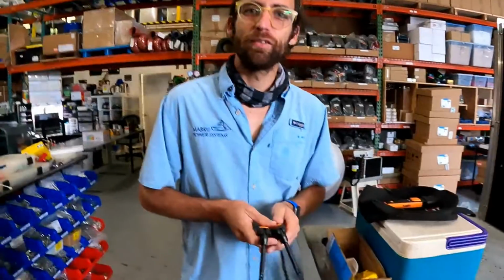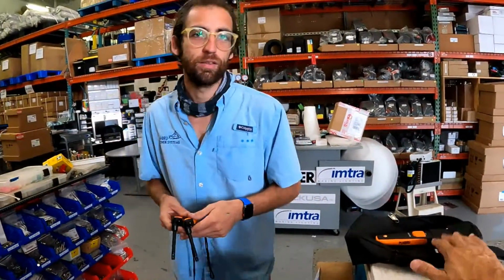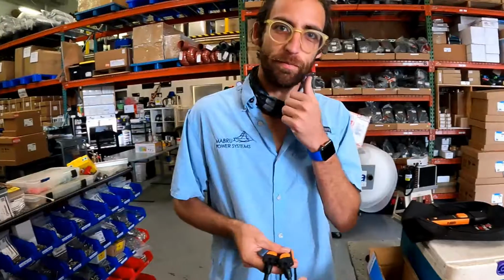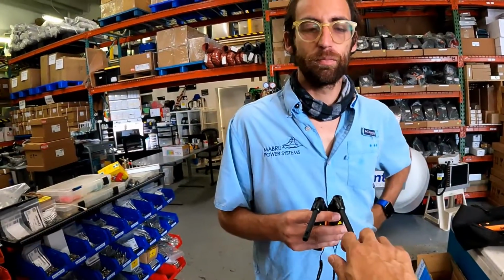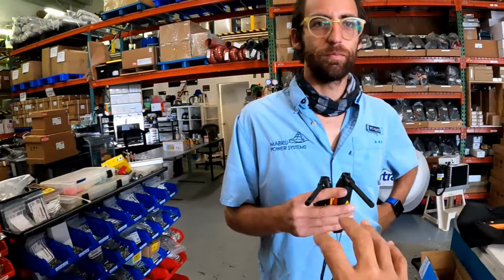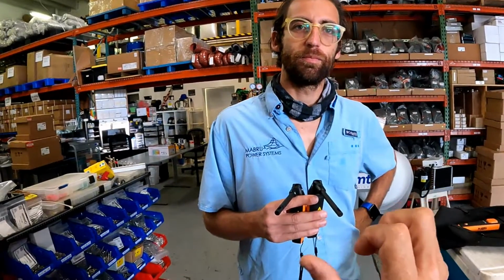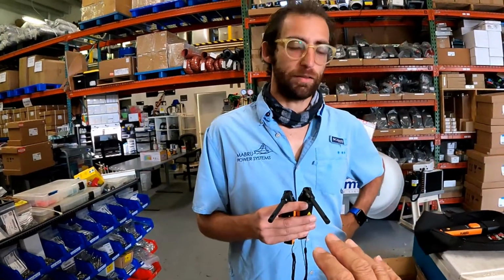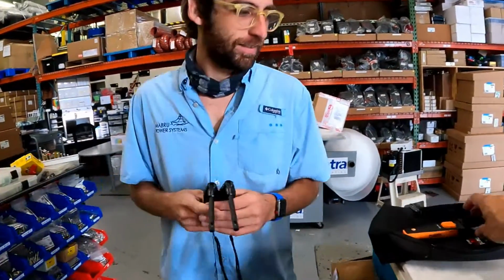Okay, we are going to refresh. With the anemometer, we are going to check the CFM, and with those sensors, one in the discharge and the other in the return, we are going to check the delta in temperature and the delta in humidity. Exactly. With those values, we are going to calculate the BTUs.